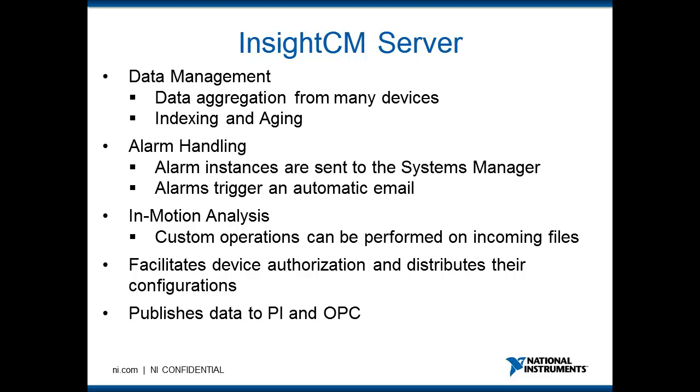So let's review the role that the server plays within the InsightCM framework. Now the server is a single system that is talking to presumably many devices. The server's job is to aggregate data from all the data acquisition devices, facilitate communication to the devices, and manage all of their configuration and images. The server can also perform analysis on incoming data files, and this is what we called earlier in-motion analysis. The server is also capable of evaluating alarms, and it also pushes data to PI and OPC UA.